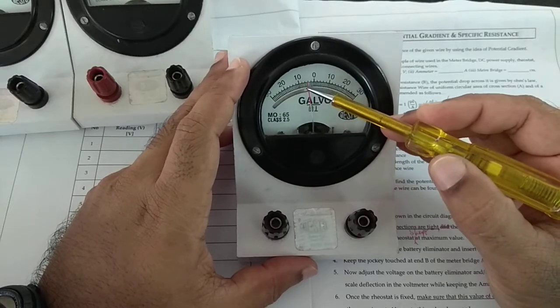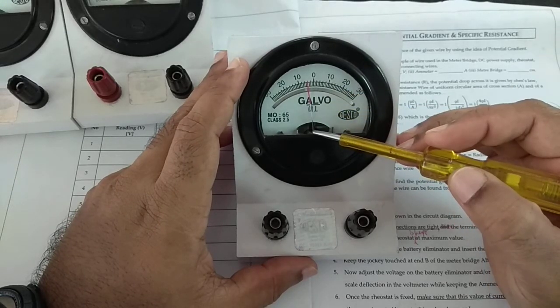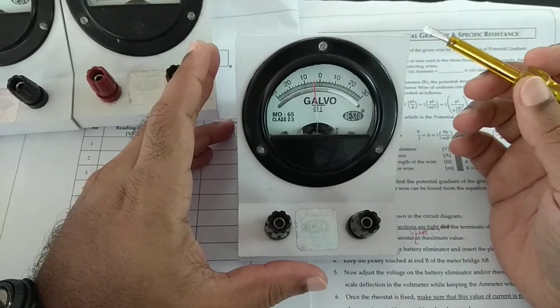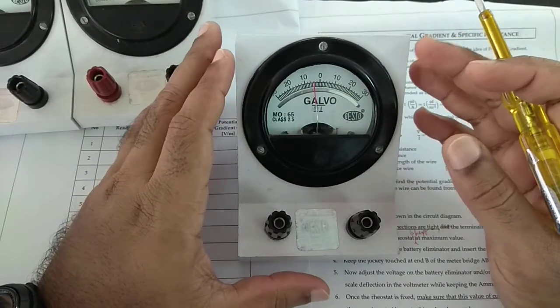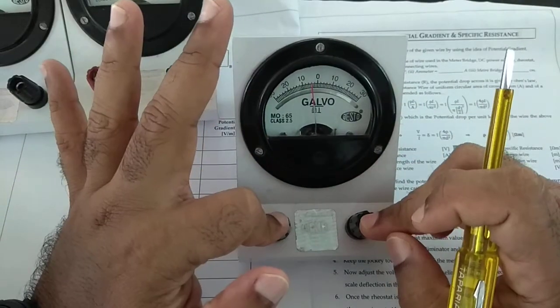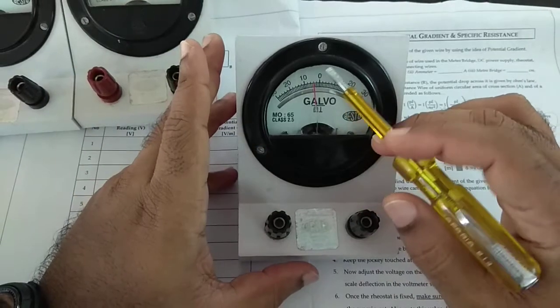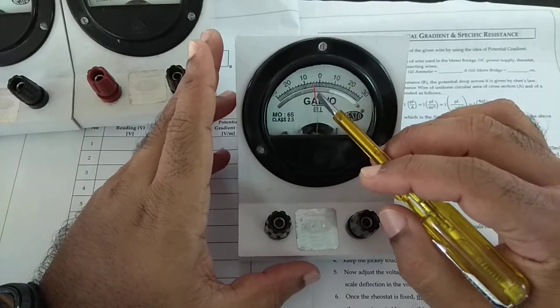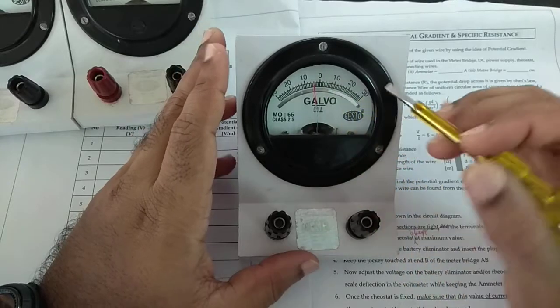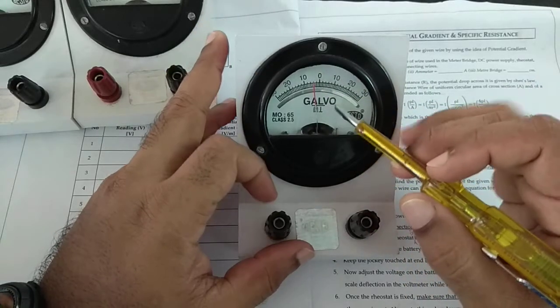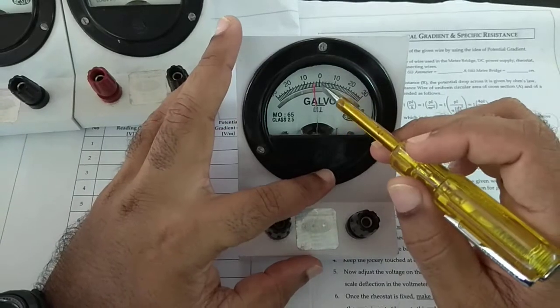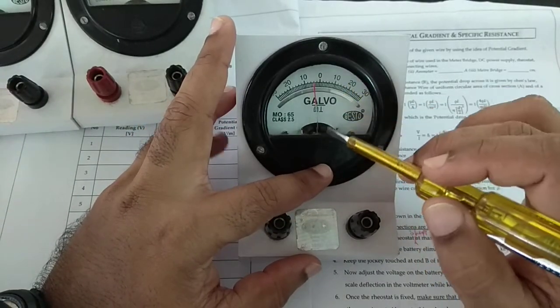You may notice that this needle is not at zero. That's not a crisis as far as the galvanometer is concerned, because a null deflection point, when no current passes through the galvanometer, is not a point where the needle is at zero. It is a point where the needle does not move at all.